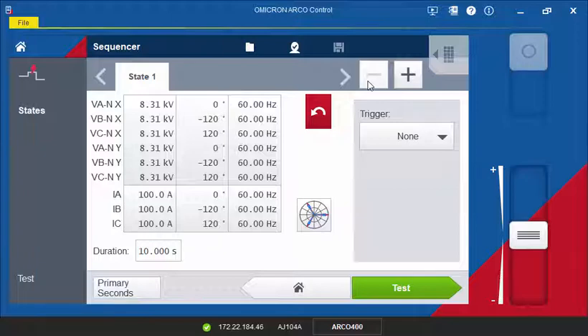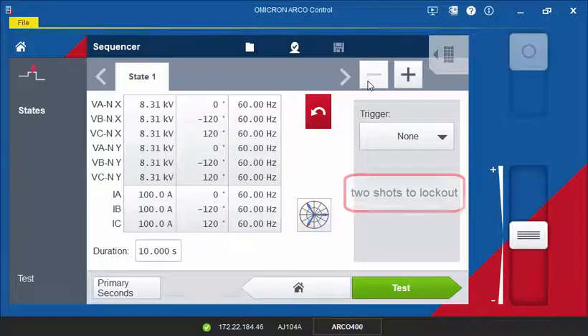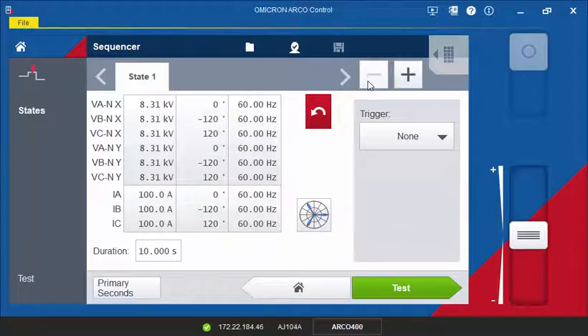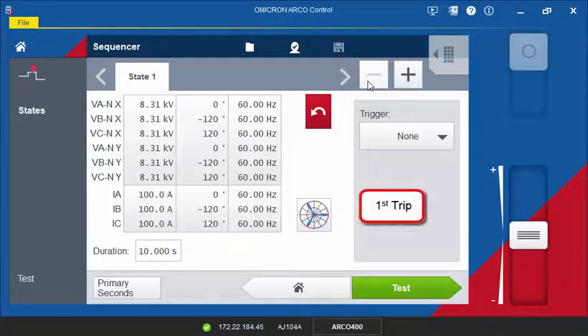In this scenario, we want to test the reclosing sequence of our controller. It is configured to two shots to lock out. We will start with a load state for a defined time, followed by a fault where the first trip will occur.